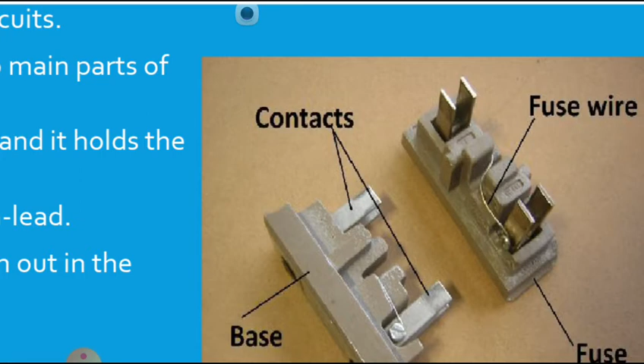Another disadvantage is low rupturing capacity, that is, the fusing capacity. For example, the fuse has 2 kVA of rupturing capacity for 2 amperes or 4 amperes. For 4 kVA, the rupturing current is only 16 amperes. That means if the current increases, the rupturing value may not increase accordingly, 2 kVA and 4 kVA, but the current is 4 amps and 16 amps. So the rupturing capacity is very low in rewirable fuses, and there is slow speed of operation.